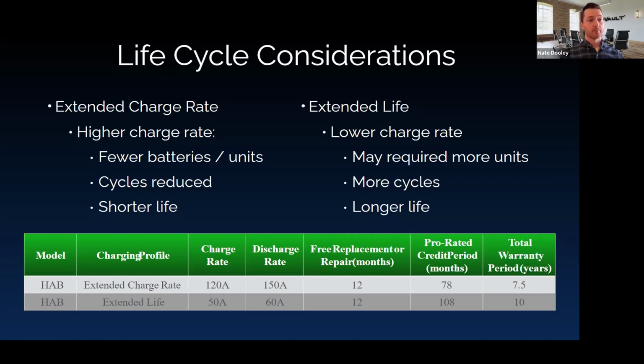But the nice thing about the KiloVault warranty is that we will support either approach. So if you have an application where you're less concerned about cycle life—maybe the battery is only used for backup applications—that might be a nice excuse to take advantage of the higher charge and discharge rate: put in only one or two batteries and charge it really rigorously when needed, or discharge it rigorously when the grid goes out, then it sits for a few months until the next utility outage.